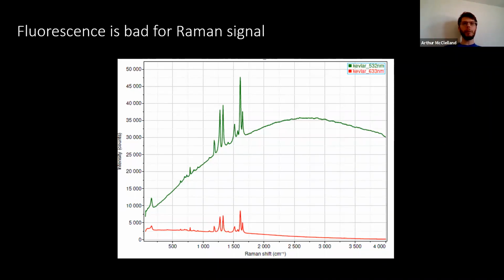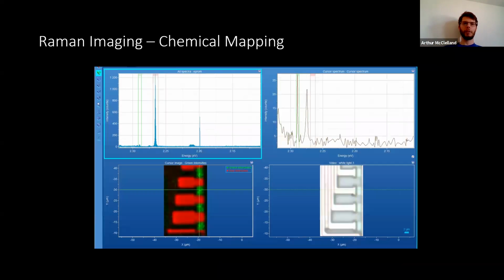So in Raman, you tend to have multiple laser lines on the same instrument, and that allows you to try to shift away from electronic resonances. You can either shift above the electronic resonance or below the electronic resonance, and that will start to decouple in spectroscopic space where the PL and the Raman show up.